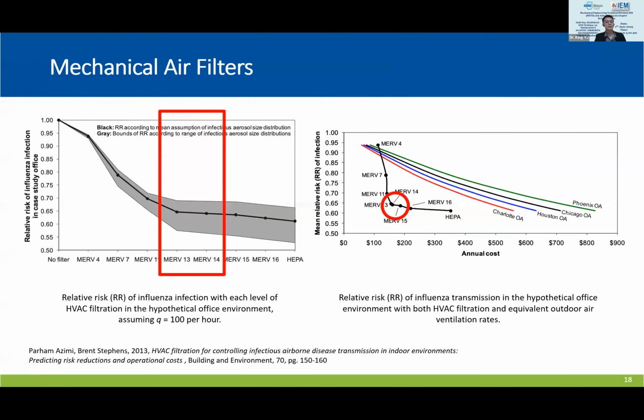For mechanical filters, we've seen a lot of recommendations for MERV 13 and 14, based on existing studies. For example, the table on the left shows the relative risk of influenza infection in a case study office. You can see that with MERV 13 and 14, the relative risk is low compared even to HEPA.